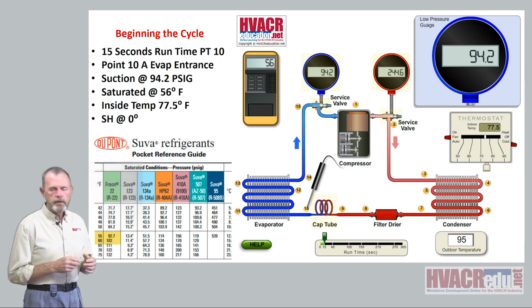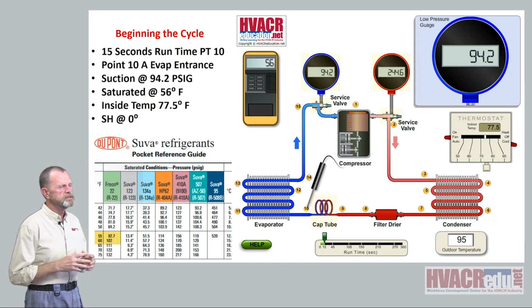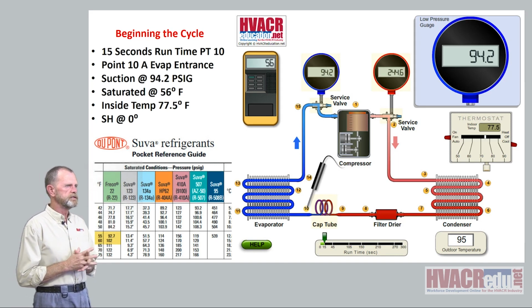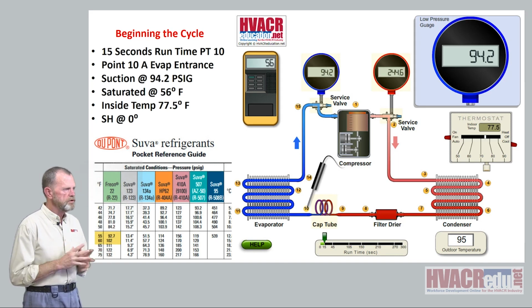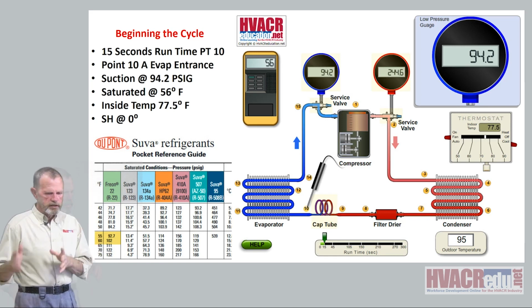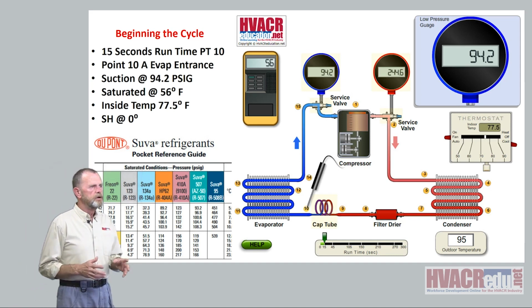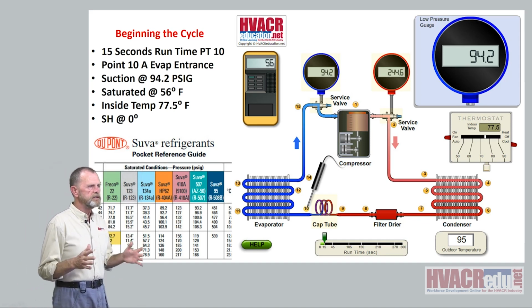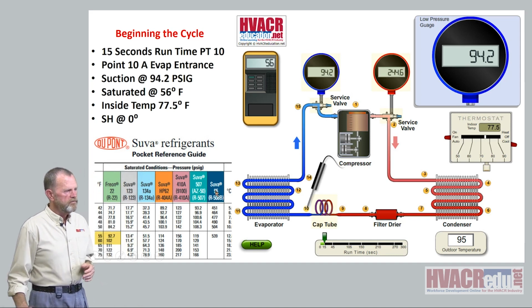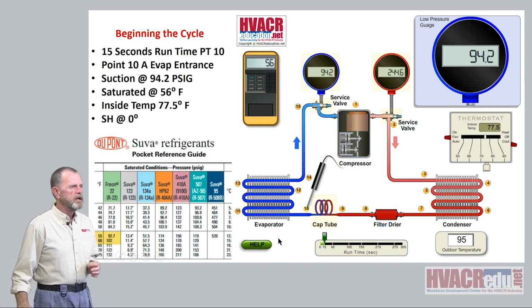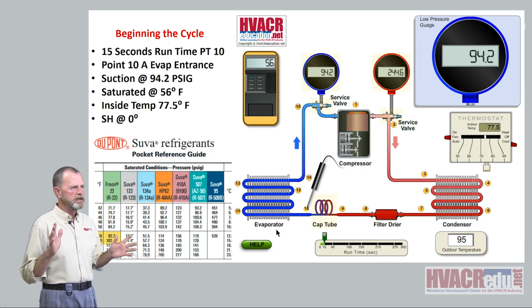And remember, we are just doing a normal cycle. I'm not going to throw any bugs into this thing yet. All right? We're also focused on the evaporator. So here I am at the start of the cycle, which means you have the greatest amount of heat available in the airflow. In this case, we're using air, in the airflow going around this evaporator coil. So we have the biggest amount of heat available to grab.